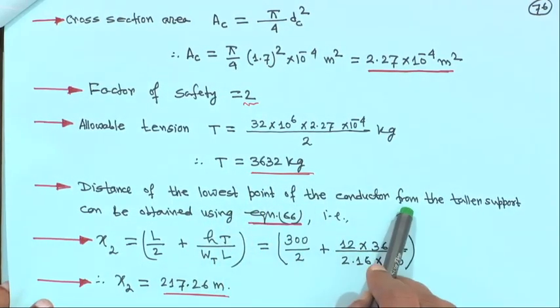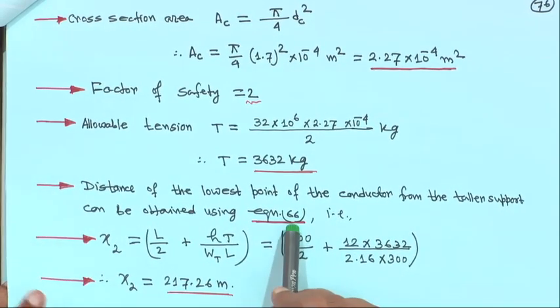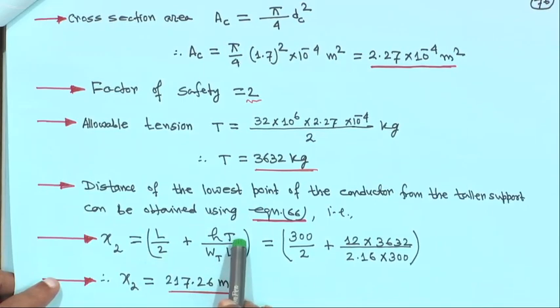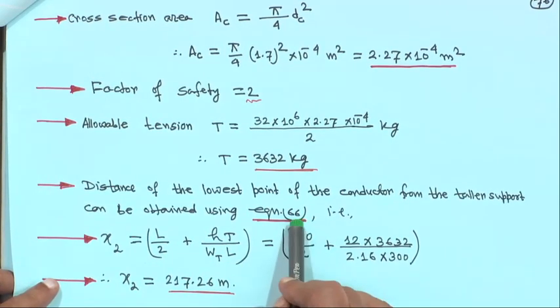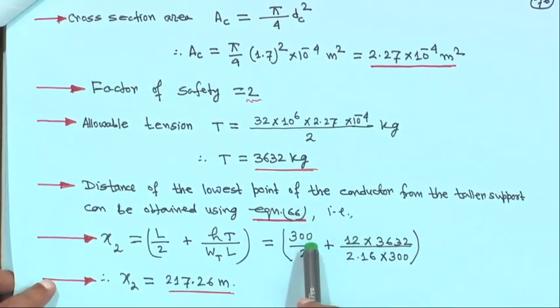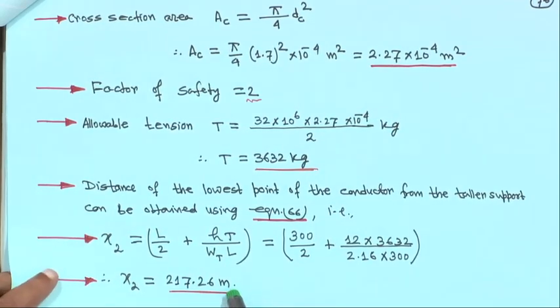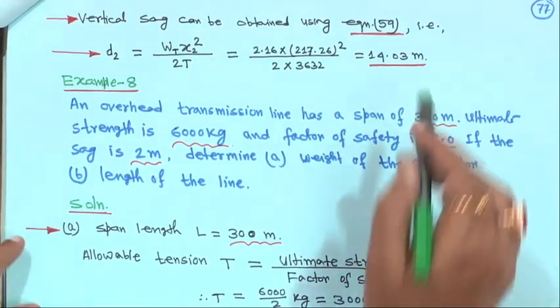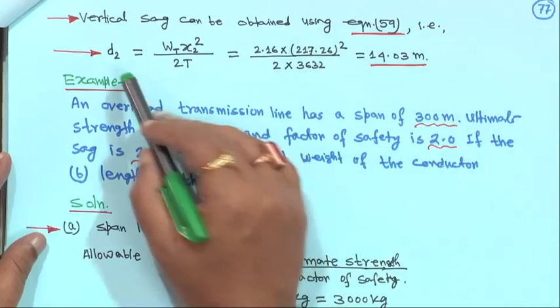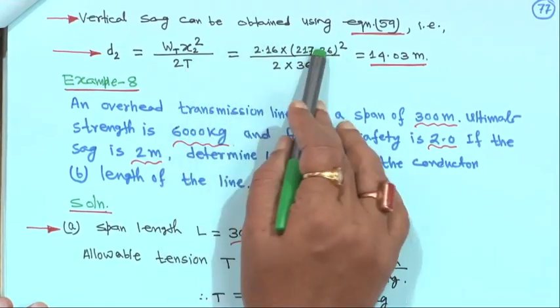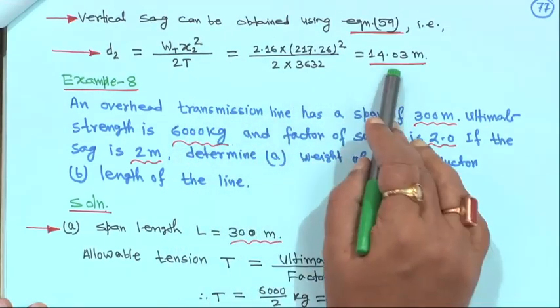Distance of the lowest point of the conductor from the taller support can be obtained using equation 66: x2 is equal to L by 2 plus h·T upon Wt·L. Substituting: 300 by 2 plus 12 into 3632 divided by 2.16 into 300, giving x2 equal to 217.26 meter. Vertical sag using equation 59: D2 is equal to Wt·x2 squared upon 2T, which is 2.16 into 217.26 squared divided by 2 into 3632, giving 14.03 meter.